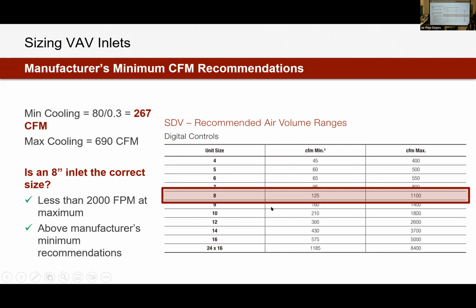Now, this minimum airflow that's set in the catalog for all manufacturers is based on a velocity pressure of 0.02 inches. It's a pretty small velocity pressure. Again, that's what we're measuring at the cross flow sensor. In another section, I'll go through a whole discussion of minimum airflows, and why we're currently cataloged here and could we actually go lower. For the sake of this example, and sizing our 8-inch inlet, everything checks out. At the maximum end, we are staying less than 2,000 feet per minute, so we're not going to have any acoustic issues. And then on the minimum end, we're staying above the recommended minimum for the catalog. So we should have good readability, measurability, and controllability on the airflow measuring station.